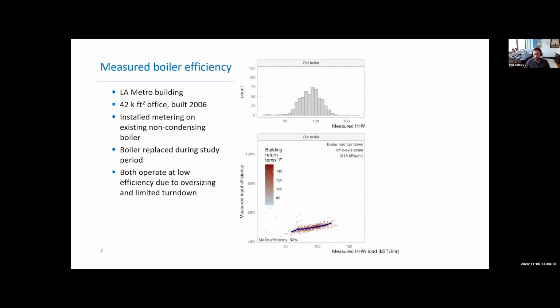One is the LA Metro office building that you're seeing here. This is a 40,000 square foot office building built about 20 years ago. And what we did is we installed metering to measure the input gas energy and the output hot water energy in this building. So we can tell how efficiently that boiler is converting natural gas into hot water delivered into the building. And you can see the results there on the image. The x-axis in the lower plot is the measured hot water load, or the output of the boiler. And then the y-axis is the percent efficiency.